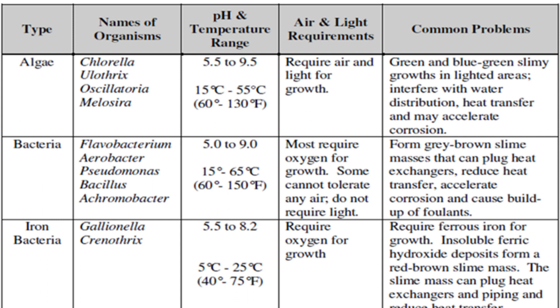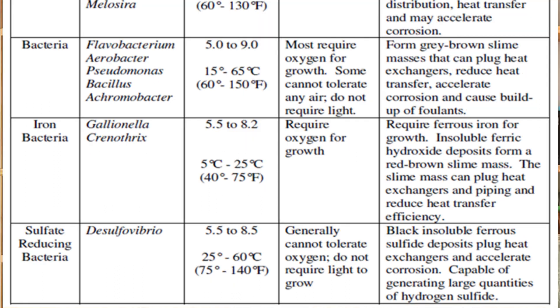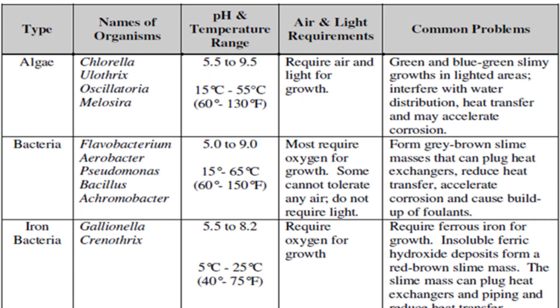Bacteria can contribute a lot of problems in our cooling water system. If these bacteria are not controlled properly, we may face a lot of problems. However, the good news is that different types of bacteria survive under different conditions. Bacterial growth is very low at low temperatures and at extremely high temperatures. Similarly, all types of bacterial growth are very low at extreme high pH and at extreme low pH.